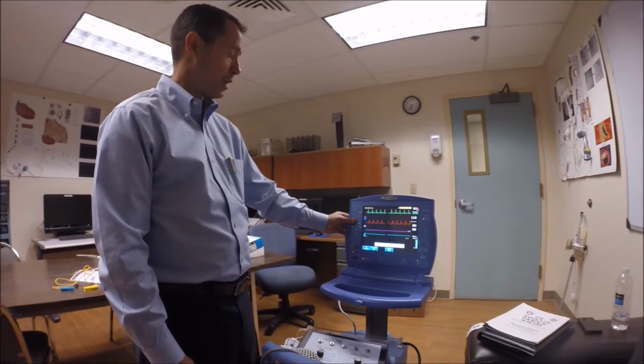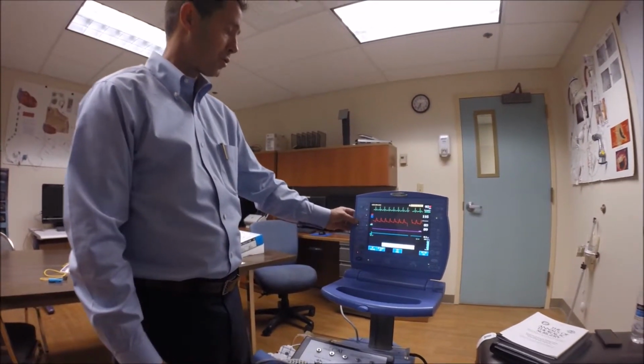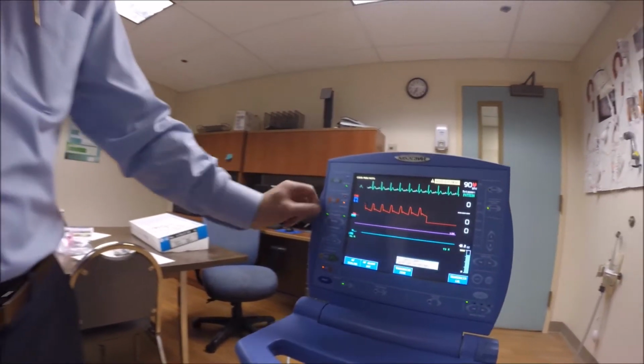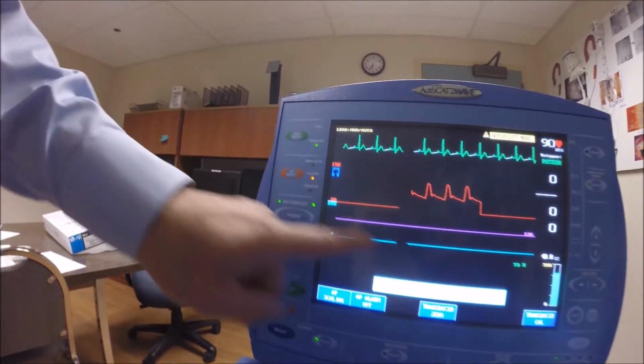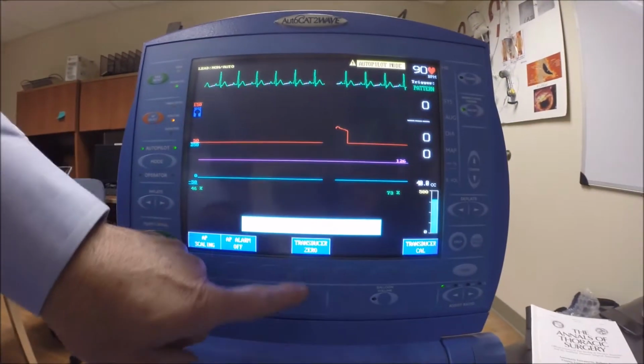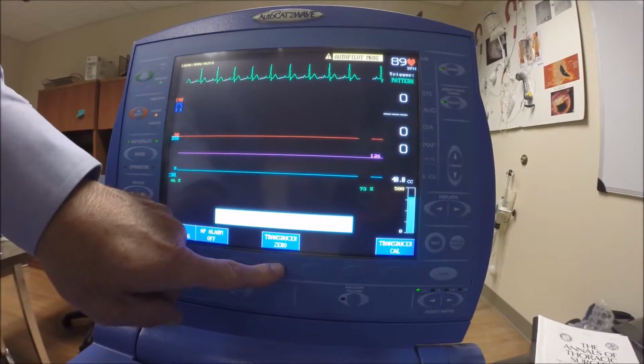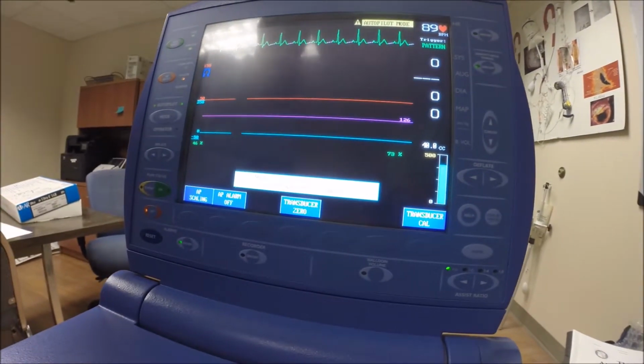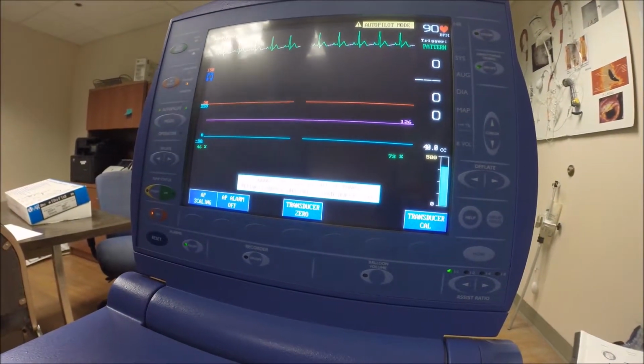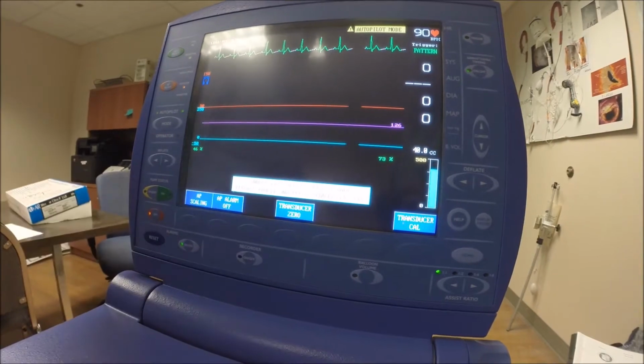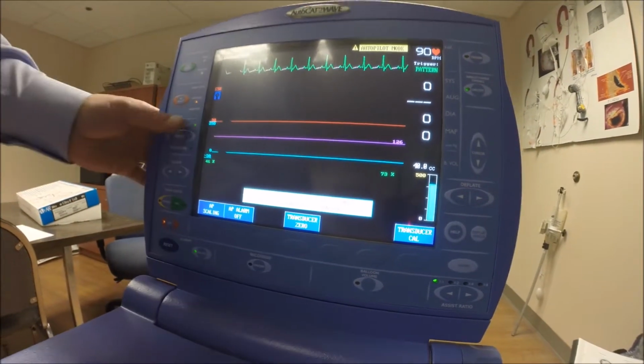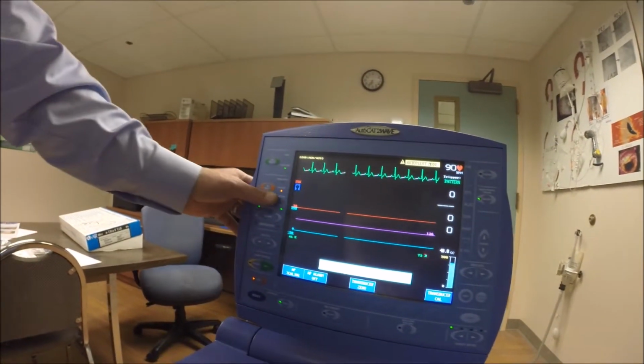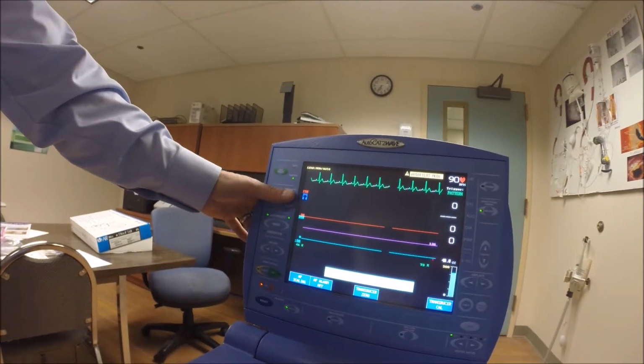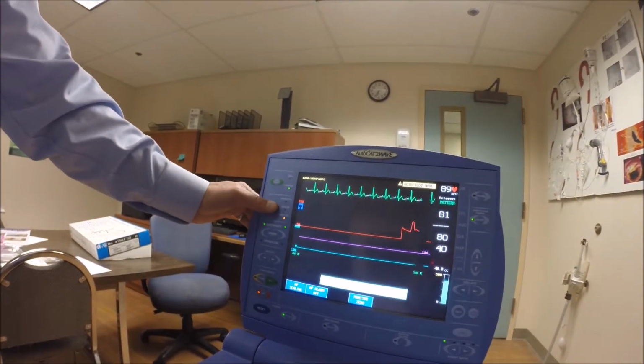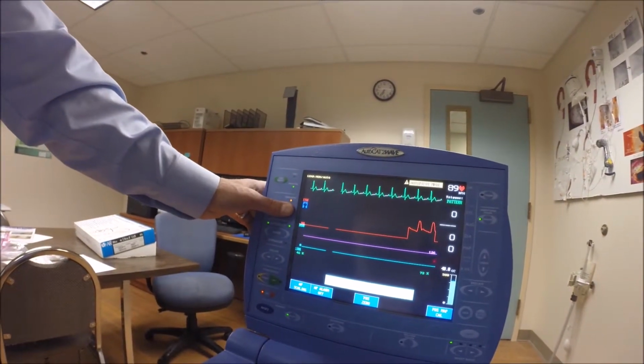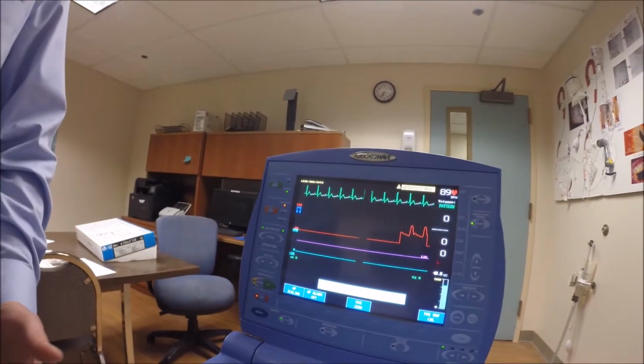So when you're transducing and need to zero your transducer, your AP select should always be on transducer, and then you'll have this bottom button here, zero transducer. You can push that and then open up your stopcock and zero it to the atmosphere, and you're good to go. And again, it'll always be on transducer. If you're using the fiber optic, then there's no need, because your fiber optic connection is always zeroed automatically.